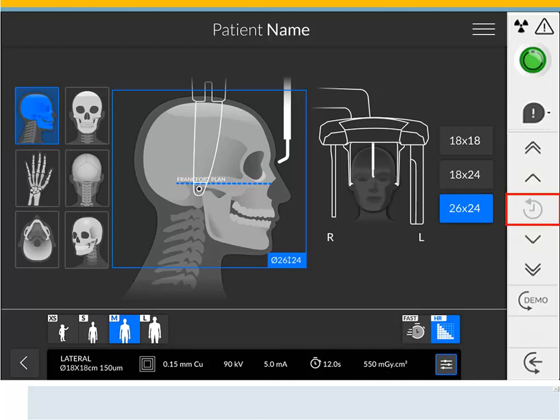Patient Data History: if a patient was previously examined, the unit will detect it from the patient's record history and this icon will turn orange. The parameter settings, patient's morphology, and the height adjustment buttons for the column will also turn orange. Accessory Notification will appear on the interface if the correct positioning accessory does not correspond to an acquisition. It turns blue if the positioning accessory is not removed and the temple supports are not rotated horizontally.